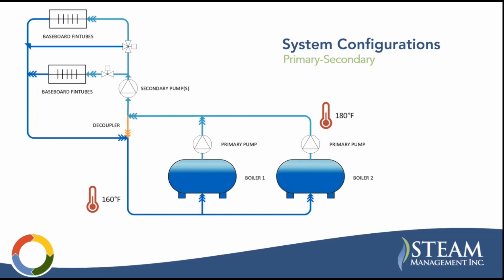Basically, you're always going to want to overpump your primary loop as compared to your secondary loop. And so you'll get some flow back through this orange line. This is called your decoupler. The decoupler can be piping, it can be a buffer tank, or they actually have products that are just decouplers to install in that location. And that's the idea here. We'll go through how this applies to condensing boilers more in a minute.